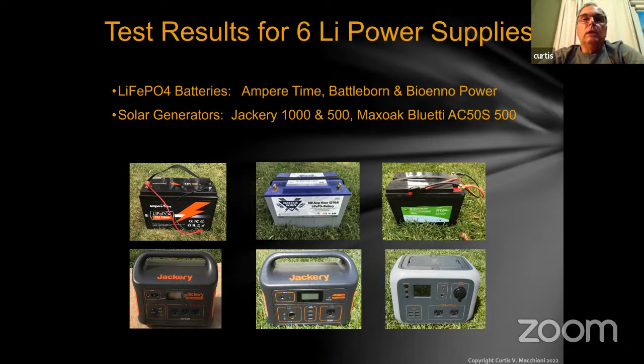I won't go through all the numbers, but this table shows the rated amp hours and the actual amp hours. I measure these by using a dummy load and running the battery down until the BMS shuts it off, so 100% depth of discharge. I do that three times to make sure the results are consistent, and they always are, with only minor fluctuation from run to run.